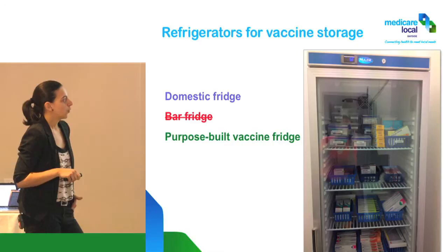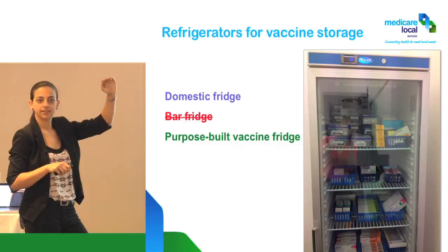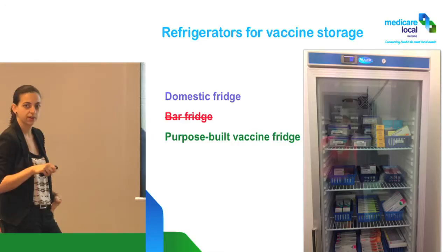We should have enough space for air to circulate. It's a bit overstocked up here near the fan — that's the fan — so this is likely the coldest shelf because that's where the cold air is coming from. I need to do a mapping of this fridge — tracking temperatures with thermometers or a data logger at different levels.